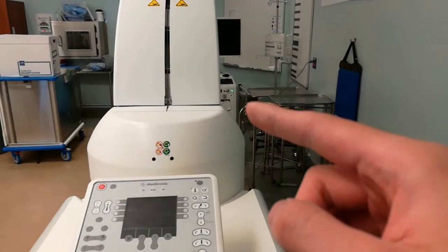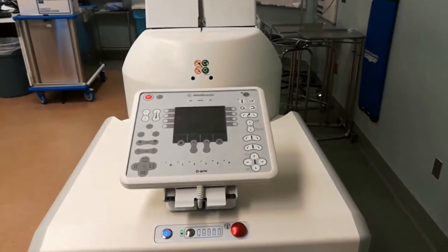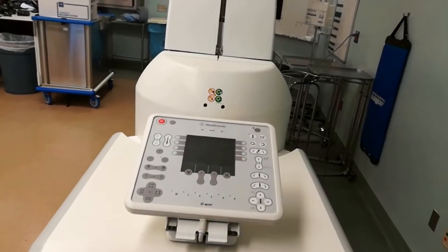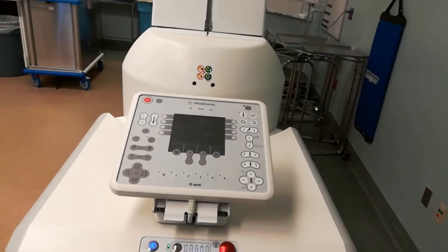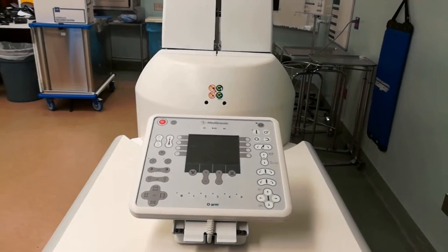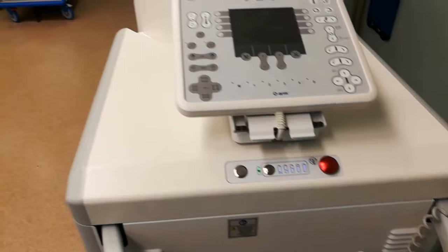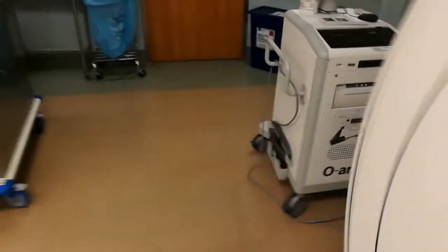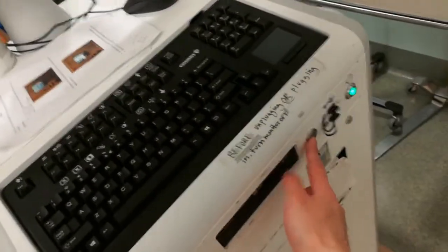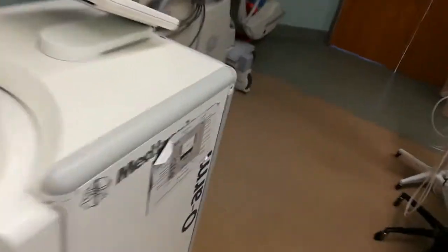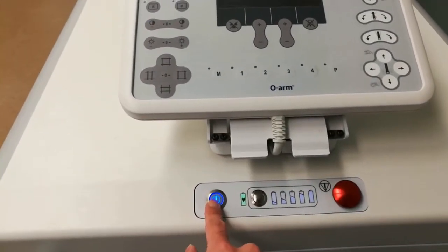Because if you just hit the on button on the workstation right now, there's a pretty good chance that these two are going to fail to communicate, and you're going to have to redo the process anyways after 20 minutes of waiting. So what I find is if you boot them up simultaneously, then they have a better chance. So what I do is I boot up the workstation first, press and hold, and then within about 10 seconds, you don't have to sprint, power up the O-arm as well.